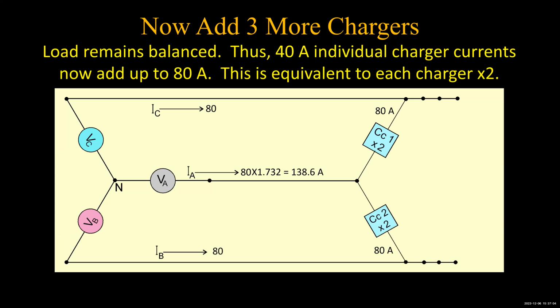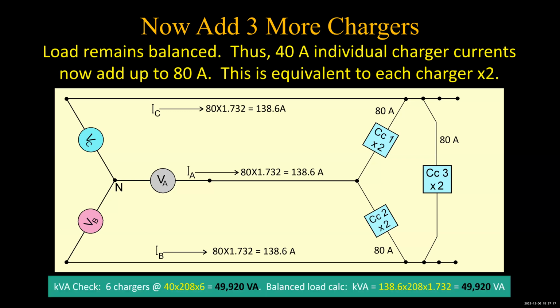Here's your 80 amps, here's your 80 amps, 138.6, another 80. All 3 lines now are balanced. So we now have 6 chargers at 40 amps each, and we've got 138.6 amps. Okay. And this is what we had before, 6 chargers. And let's just check it out here. The kVA for the total load, 40 times 208 times 6, is 49,920 volt amps. Yeah, 40 amps, that's 208 volts. And we've got 6 of them. So that's 49,920 actual volt amps consumed by the charge controllers.